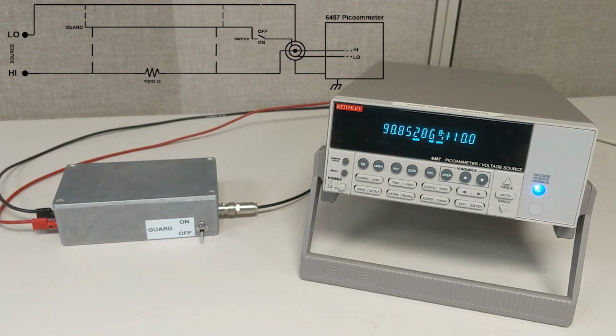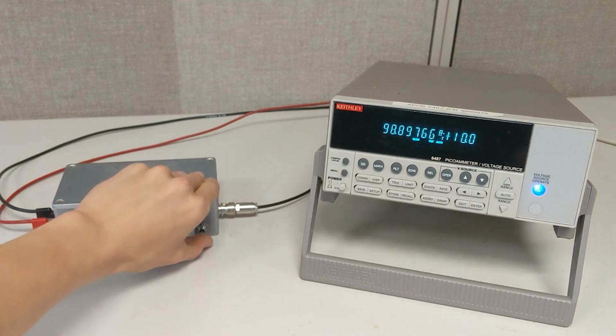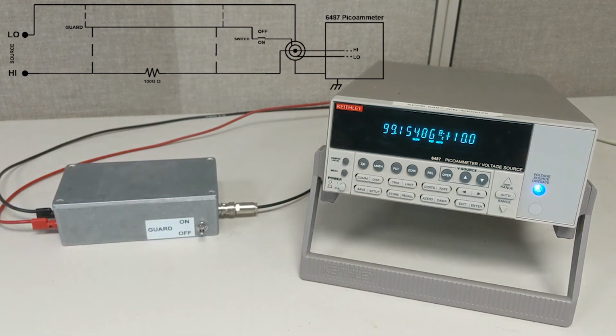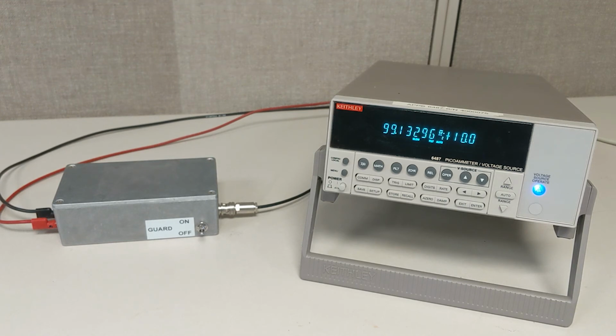This measurement is close to the expected 100 gigaohms of the demo box's resistor, but let's see what enabling the guard can do to improve our measurement. With the guard now turned on, we observe an increase in resistance to approximately 99.1 gigaohms. Based on our results with guarding enabled, we see a noticeable change in measurement closer to the listed value of the resistor. This measurable difference is due to the guard line removing the leakage current path.